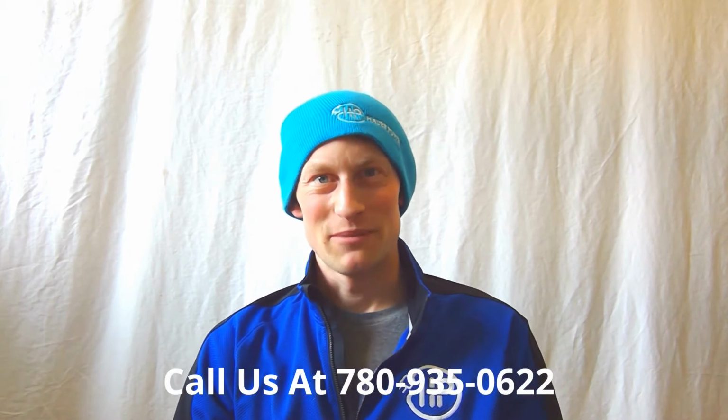I'm the founder here at Hauer Power Electric, and it's my job to keep all of our workers busy and working productively and safely. So that's why I wanted to reach out to you guys today. As far as safety goes, if you have an old Federal Pacific panel, with those old black style breakers, you may want to change those out. They are known to be a fire hazard, and after doing some research on it, it's more common in the United States, but here in Canada, we also have the issue of breakers that fail to break the circuit.